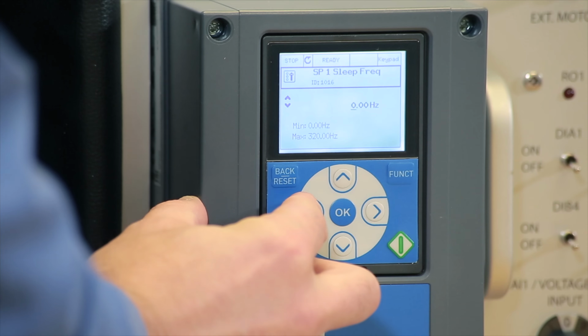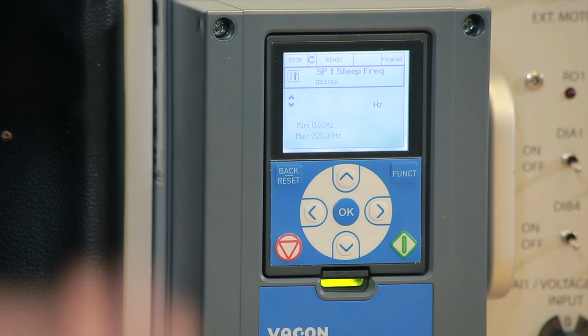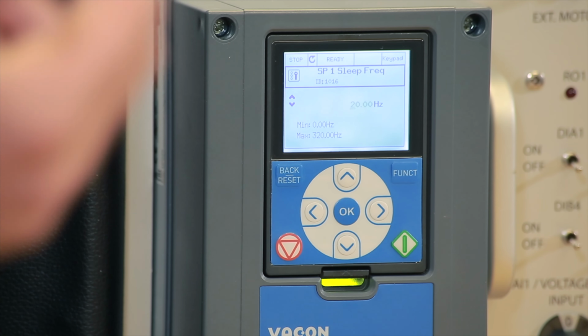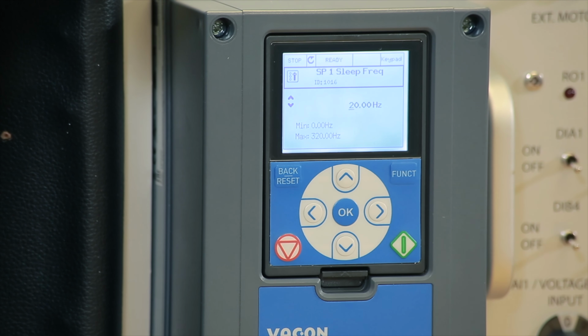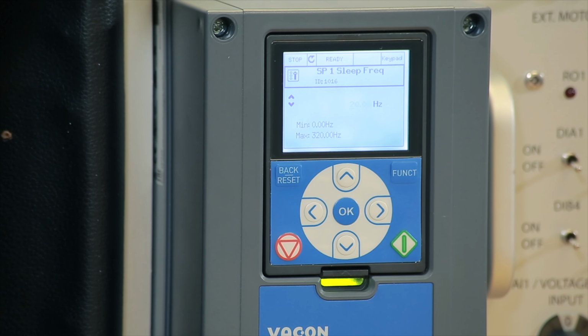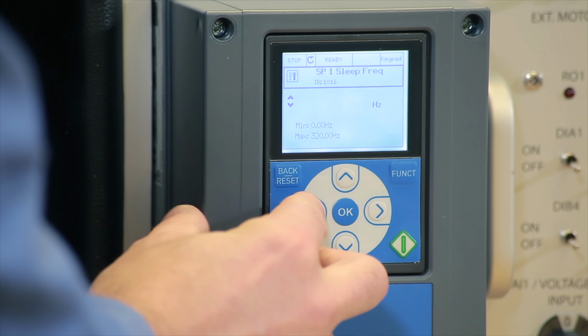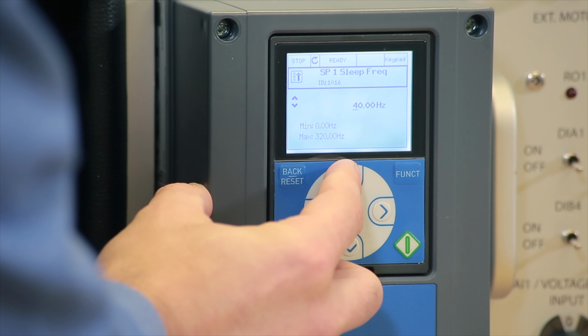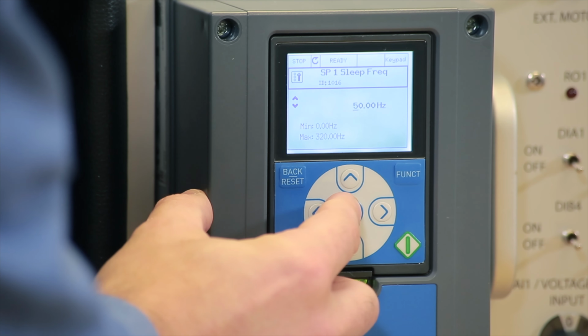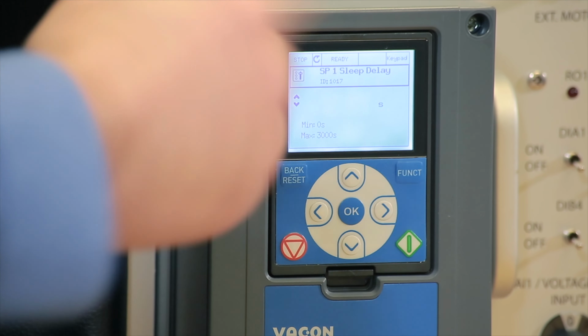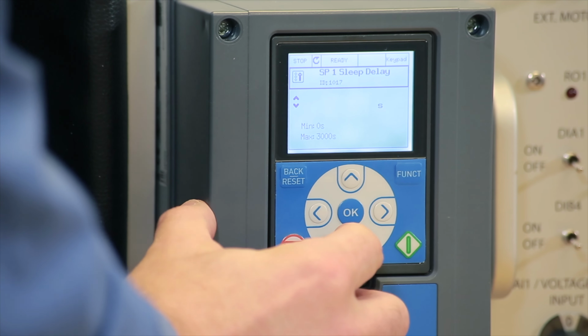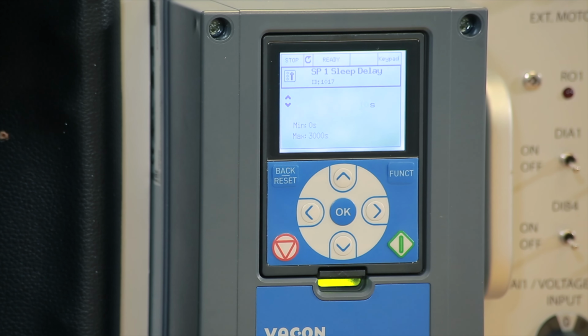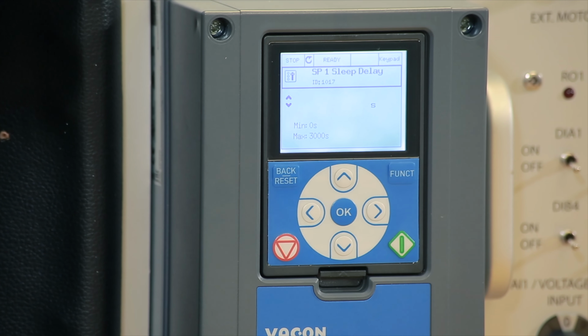So, sleep frequency. Now, we can say for our case scenario that when the drive starts slowing down from 60 Hertz, and if our minimal speed, for example, is 40 Hertz in a future application, we want to start the counter, let's say below 55 or below 50 hertz. So as an example here, we're going to use below 50 hertz. And for how long? In our demonstration case, we're going to change the seconds to 10, but in real life you can program it whatever you like. In the sleep frequency, you could change it to 40 hertz, 45, whatever the application demands.